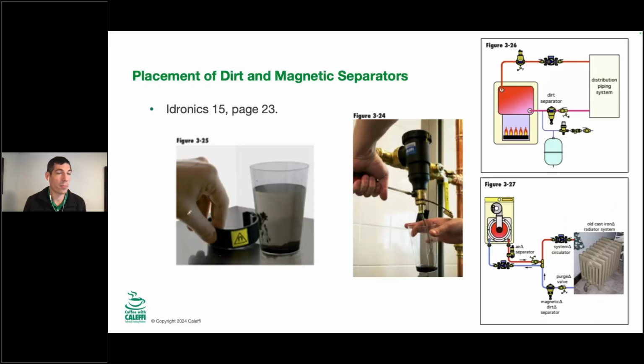Okay, here's what I would recommend if you're going to blow down these devices. Do that into a cup, or a white bucket if it's a big system, and then take a magnet and see how much of that debris reacts to it. If you've got a lot of stuff that's following around a magnet on the bottom of the bucket, and you continue to see the same amount over and over again, there is air in that system that is rusting the system from the inside out.